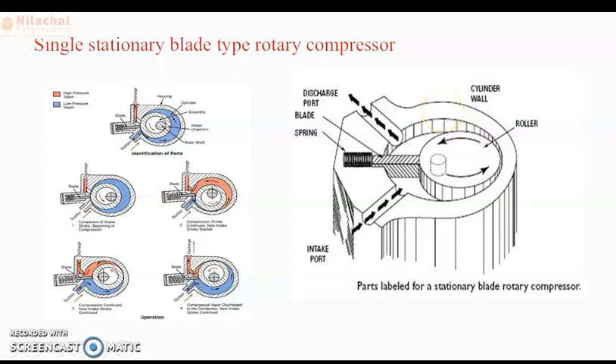The single stationary blade type rotary compressor consists of a stationary cylinder, a roller, and a shaft. The shaft has an eccentric on which the roller is mounted. A blade is set into a slot in the cylinder in such a manner that it always maintains contact with the roller by means of a spring. The blade moves in and out of the slot to follow the roller when it rotates.